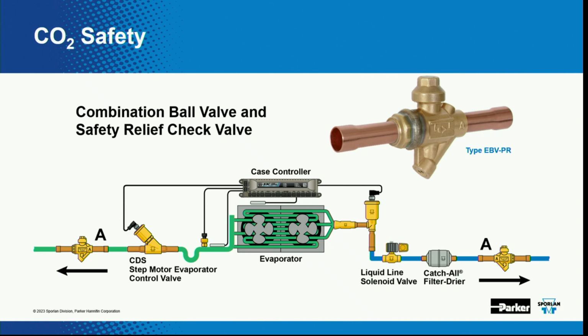So that's a good intro to our ball valve. Sporlan makes a ball valve that has a built-in relief valve. It's a check valve. So you'll see these on the system. There's a little A right there. You just need to make sure that you point the A towards, like in this case, your coil, because there's a lot of refrigerant in there that we want to be able to get out of there if it needs to.